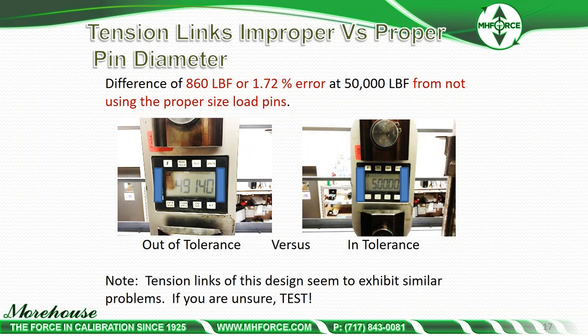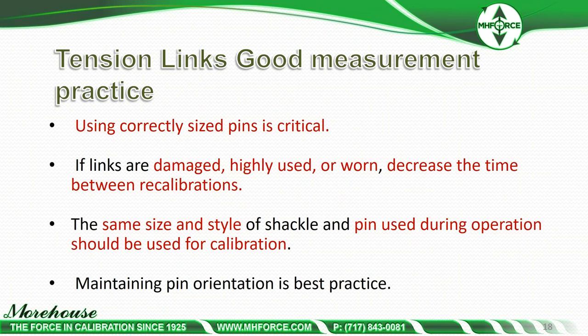Not to pick on Dillon — tension links of this design seem to exhibit similar problems. Almost every tension link of this design we've seen — Dillon, Tractel, all of them — has the same error. The way to avoid it is to send whatever you're using with it in for calibration and let the lab use the exact pins you're using. Dillon acknowledged this and said: using correctly-sized pins is critical; the same size and style of shackle and pin used during operation should be used for calibration; and maintaining pin orientation is best practice.